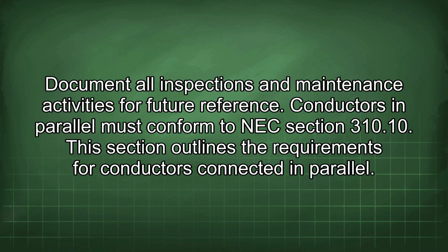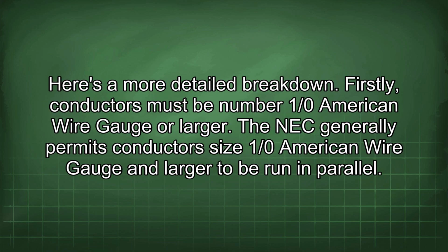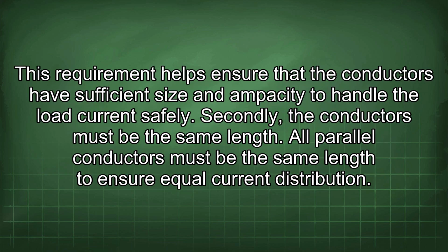Conductors in parallel must conform to NEC Section 310.10. This section outlines the requirements for conductors connected in parallel. Here's a more detailed breakdown. Firstly, conductors must be number 1/0 American wire gauge or larger. The NEC generally permits conductors size 1/0 American wire gauge and larger to be run in parallel. This requirement helps ensure that the conductors have sufficient size and ampacity to handle the load current safely.